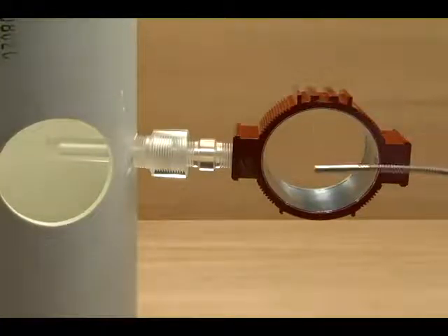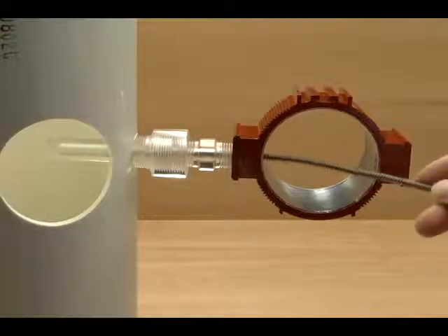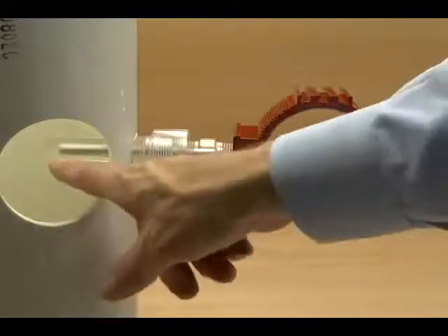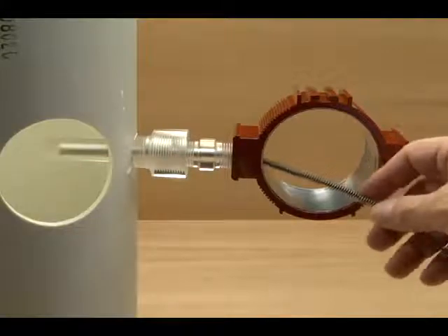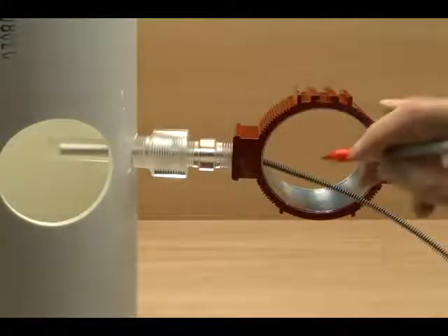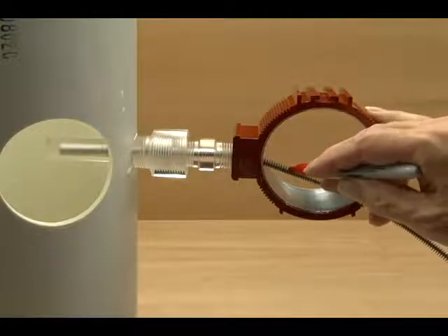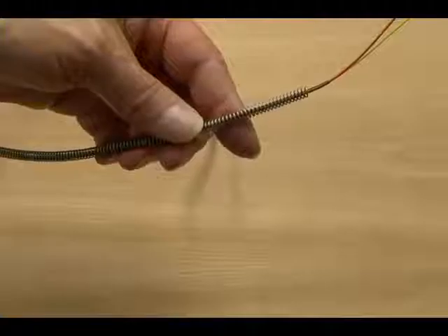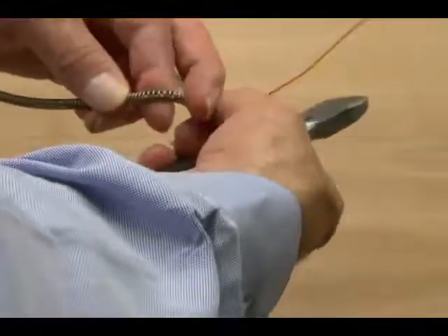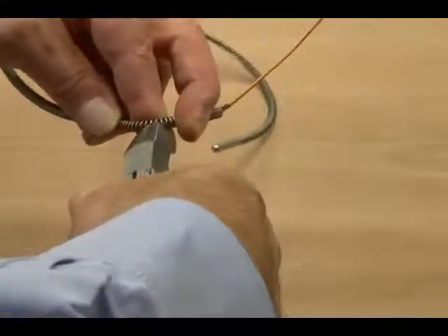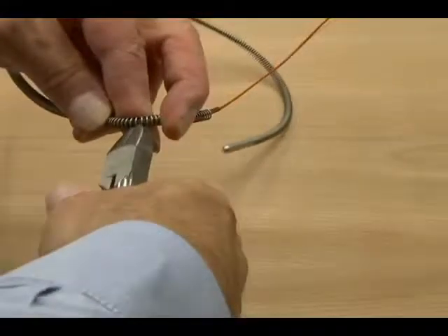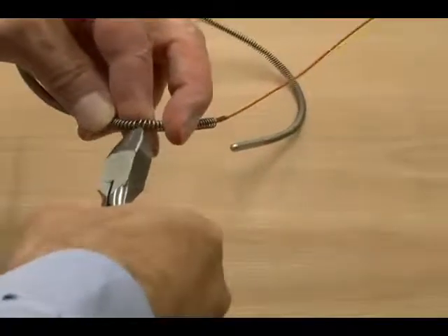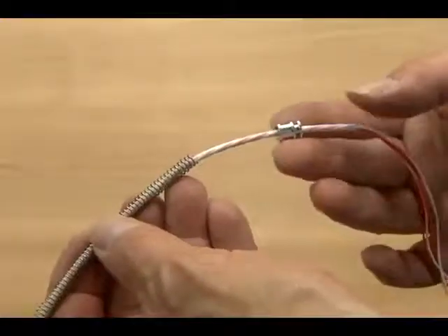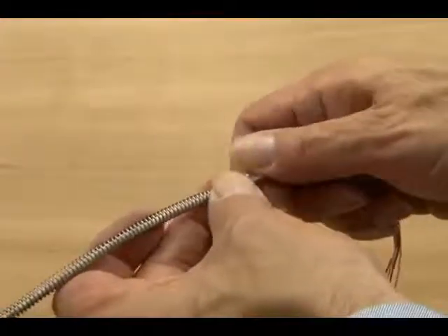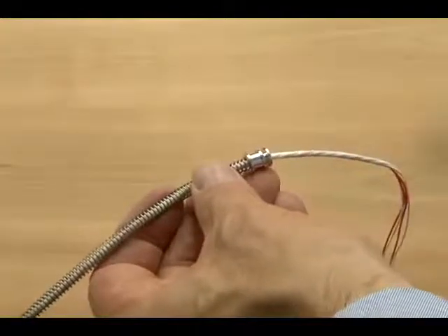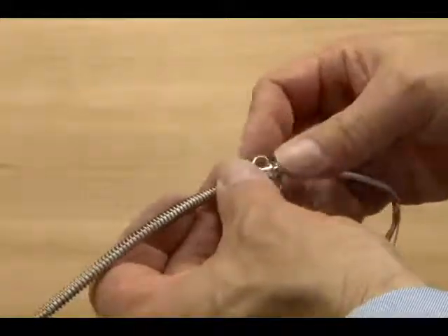Simply insert the worm into the thermal well and push it all the way in. When the probe bottoms out, mark the spring about an inch or so beyond the housing, so the spring is a bit over length. Cut it carefully with a pair of wire cutters so you don't damage the signal wires. There's a cap in each kit that fits over the end of the spring where you cut it off. Put it in place and then attach this little spring clip with the prongs pointing toward the probe end.